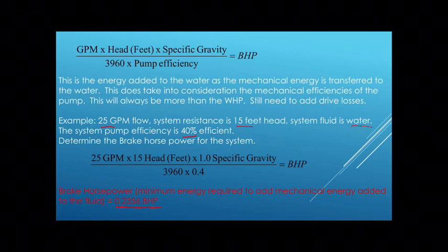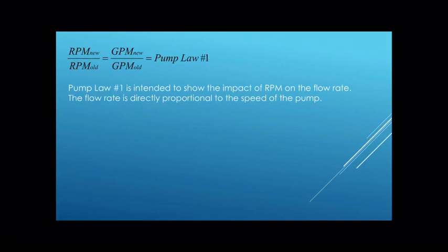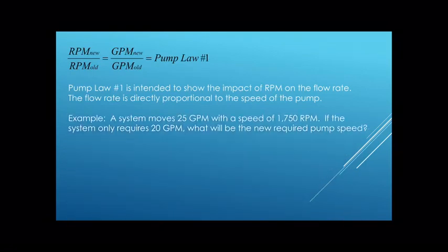This formula will work almost to the T. If you were to look at every single manufacturer's pump curve, and as long as you know what their efficiency is, you can figure out exactly what that brake horsepower is. What kind of horsepower demand is it going to take to do this work? It is spot on the money.